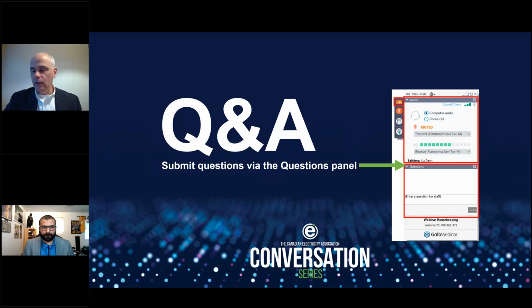The other part, I think, is a question about capability to detect fault and isolate. Upon receiving command from the controller, whatever the sensing, time characteristic, relay and protection, from receiving the command to complete execution, extinction of the arc is 40 milliseconds. So that's the total clear time from command to execution. I think that's what the question was implying. Yeah, perfect. Thanks for that.